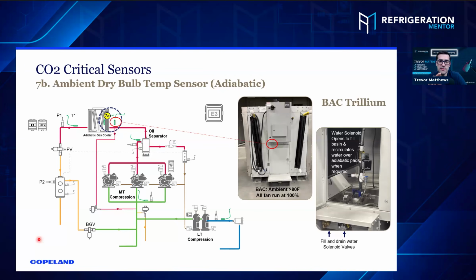Water control is the ambient one, and the fan speed above 80. Right. Correct. Okay, so does it switch? Do you know if that, because right now 7A is controlling the fans when it's in subcritical. When it goes over 80, it switches from 7A to 7B. Yeah, you don't need the TD control anymore because you're at full speed. Yeah.